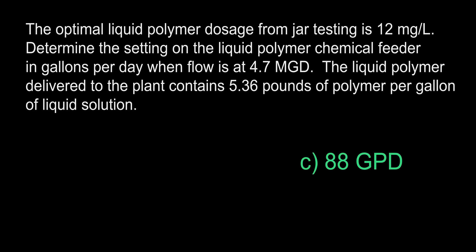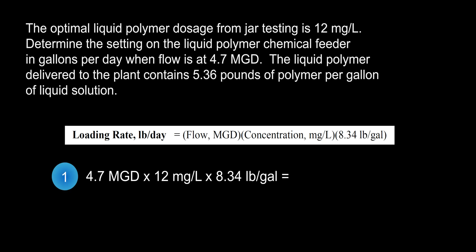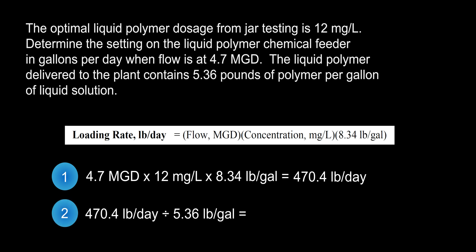The answer is C, 88 gallons per day. This question can be broken down into two parts. For the first part, we use the loading rate formula, which tells us how many pounds of polymer are required daily at the given flow and optimal dosage. For the second part, we solve by taking our previous answer and dividing it by pounds per gallon of polymer liquid solution — 470.4 pounds per day divided by 5.36 pounds per gallon — which equals 88 gallons per day of polymer, or C, our final answer.